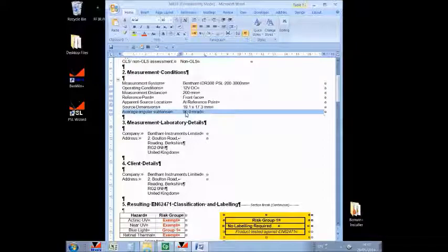So it's 19.1 at 200 millimeters and 17.3 millimeters at 200 millimeters, the average of those two angles. The 90.9 is below the 100 milliradians of the blue light exempt risk group, and therefore no apertures were required in the measurement.